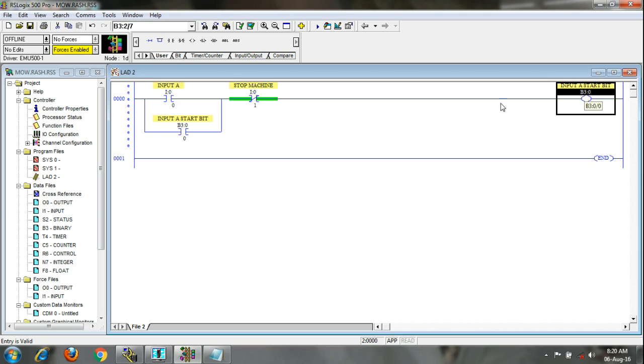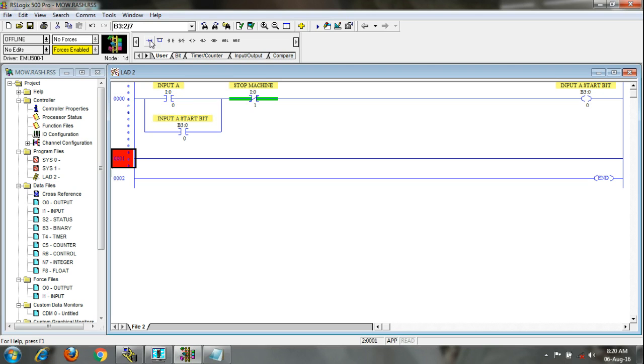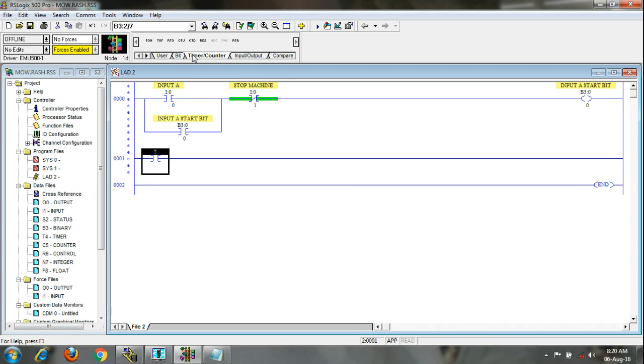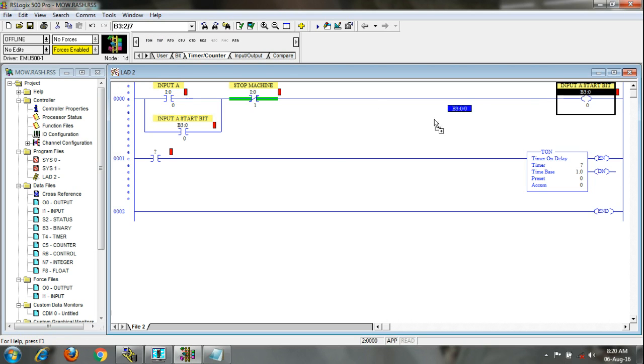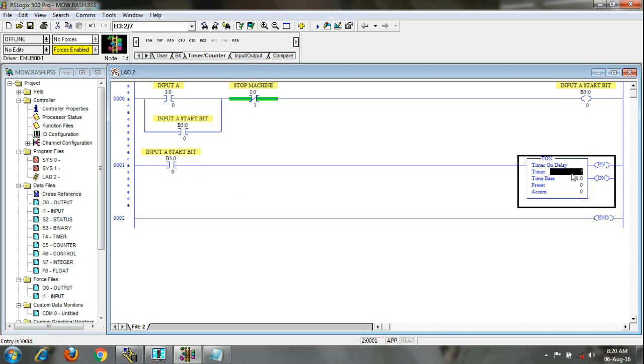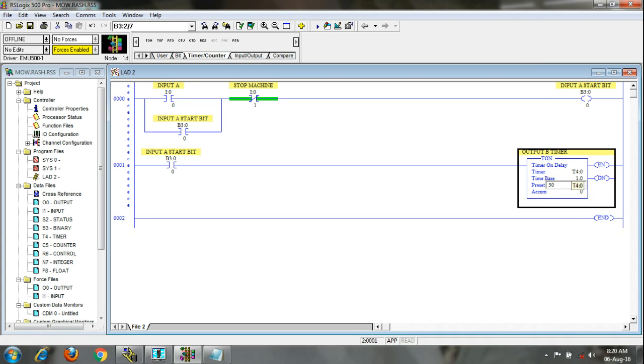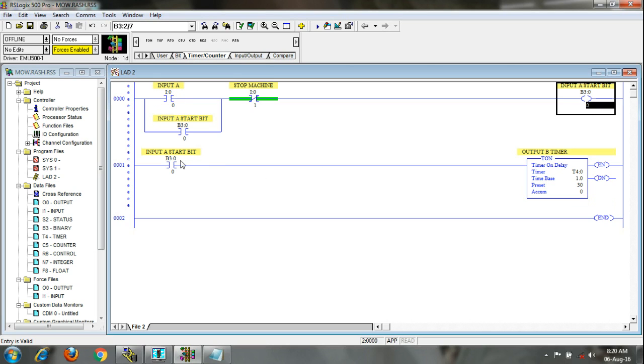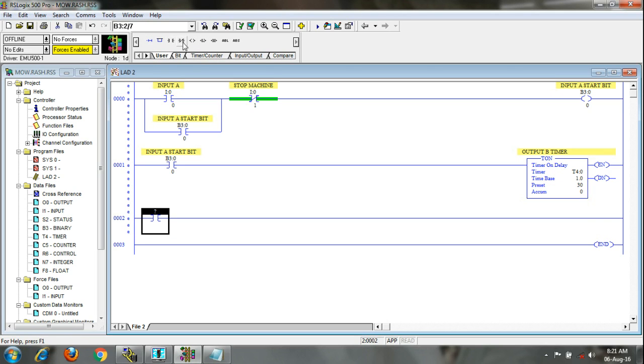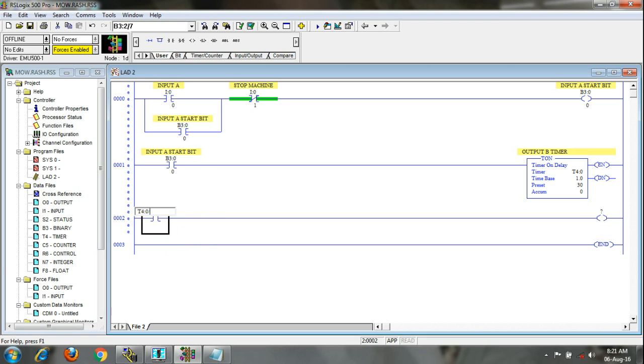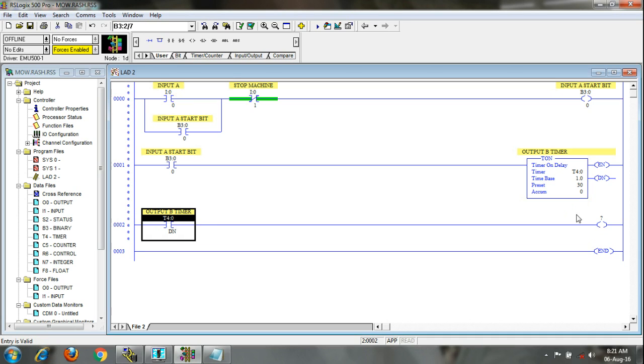After this bit goes high, a timer will run. I am taking a TON over here. When you start this bit, the pulse comes here, and I am giving the timer address — 30 seconds — this is the output B timer. When this bit goes high, the timer turns on. After 30 seconds the output will be on. So T4:0/DN — this is the output B timer done bit — and I have to take the output over here. This is our output.